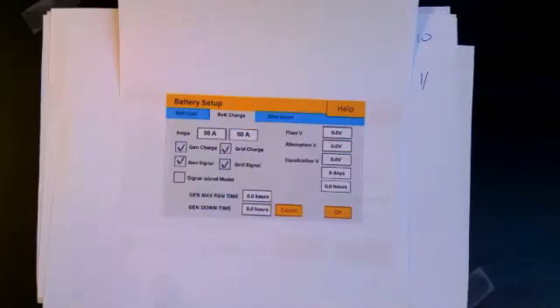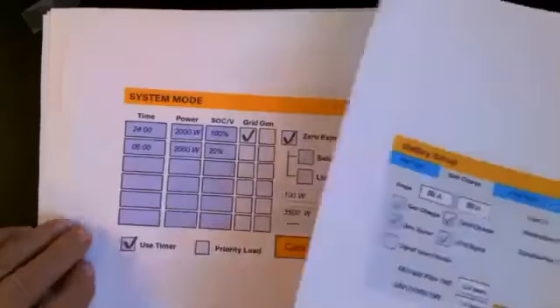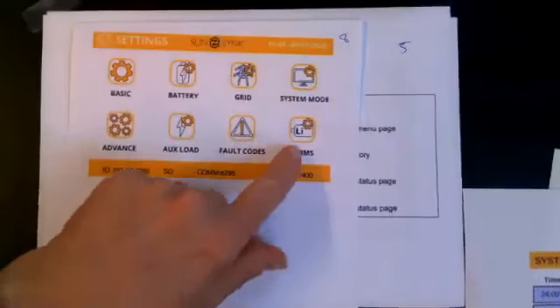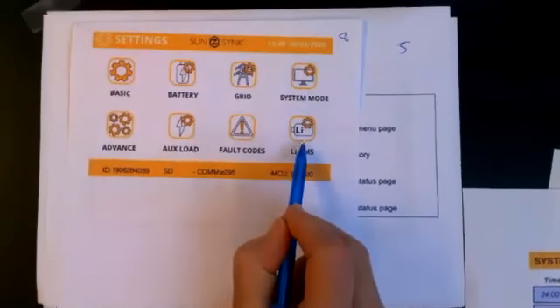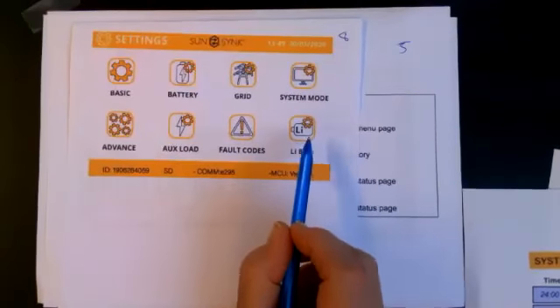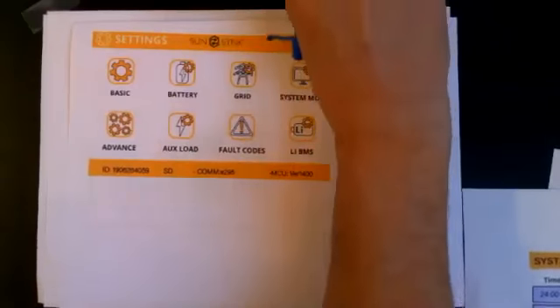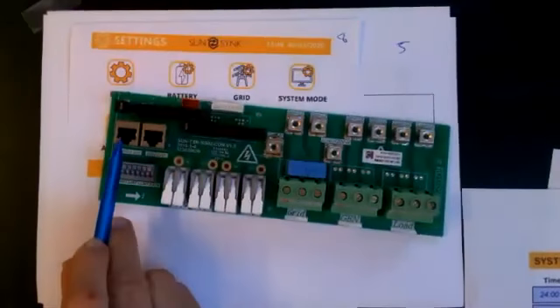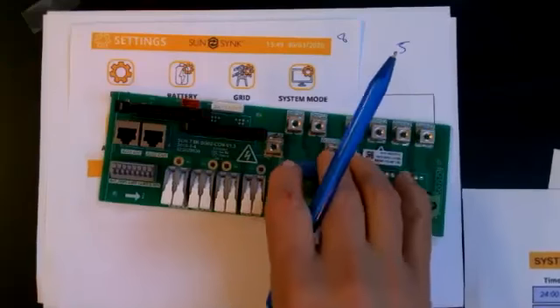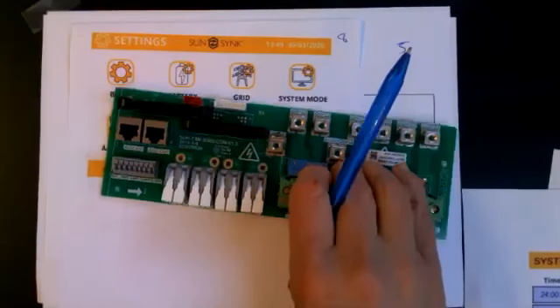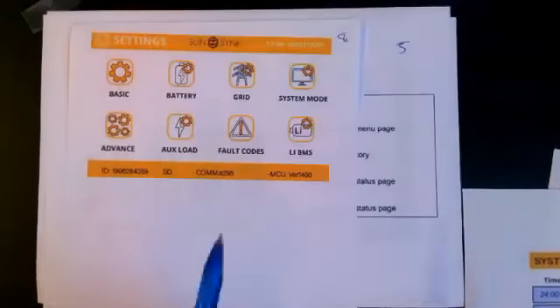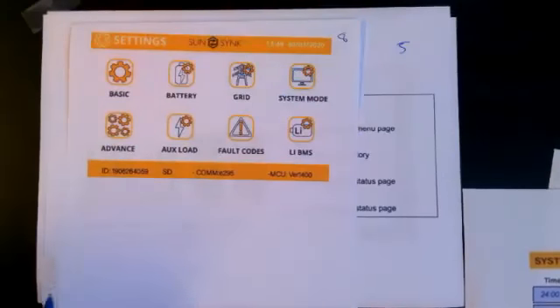When you're running with a lithium battery, and we'll just focus on the lithium battery, you must make sure you've got communications. Absolutely must make sure you've got communications. This is the check your communications page. You put your cables in, so you put your connection here to your battery, whether it's a CAN bus or an RJ45 or whatever. You have to follow the battery specification, and you must make sure you have communication.